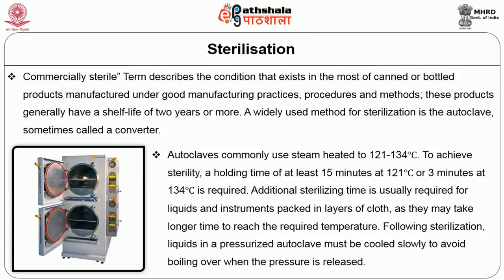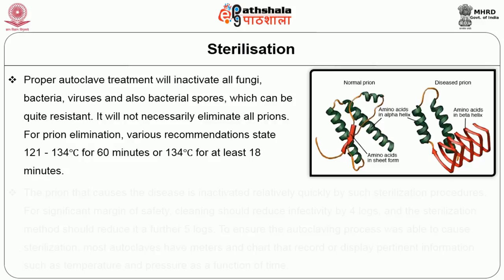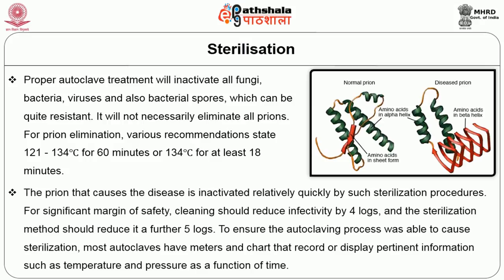Following sterilization, liquids in a pressurized autoclave must be cooled slowly to avoid boiling over when the pressure is released. Proper autoclave treatment will inactivate all fungi, bacteria, viruses and also bacterial spores, which can be quite resistant. It will not necessarily eliminate all prions. For prion elimination, recommendations state 121 to 134 degree Celsius for 60 minutes, or 134 degree Celsius for at least 18 minutes is required. For a significant margin of safety, cleaning should reduce the infectivity by 4 logs and the sterilization method should reduce it by a further 5 logs.